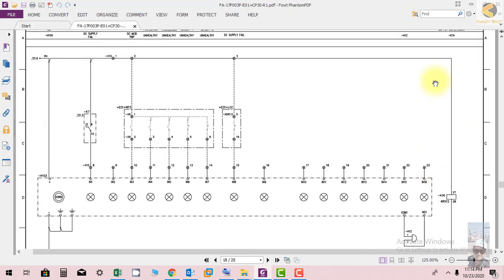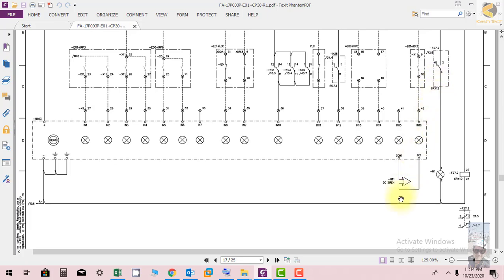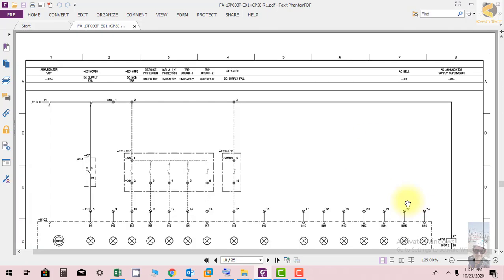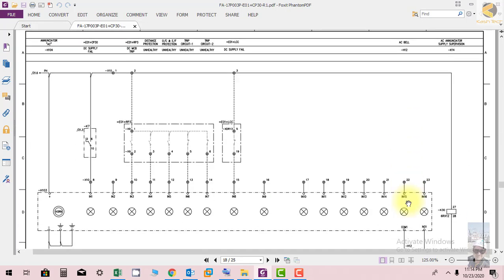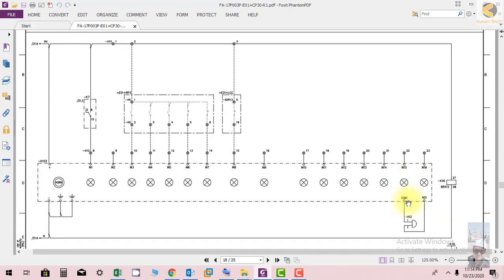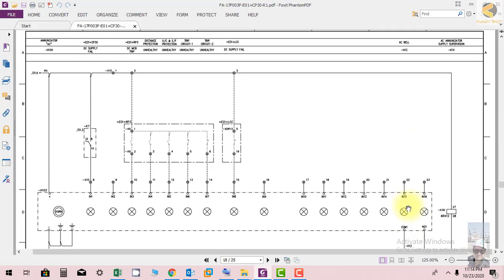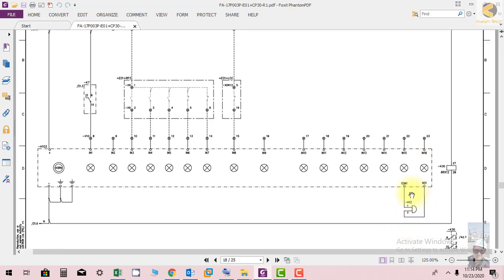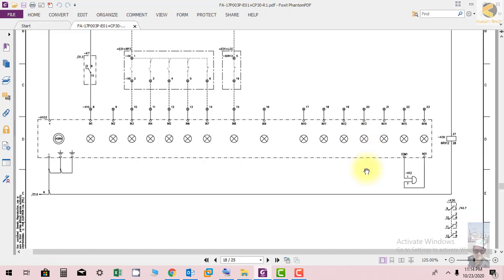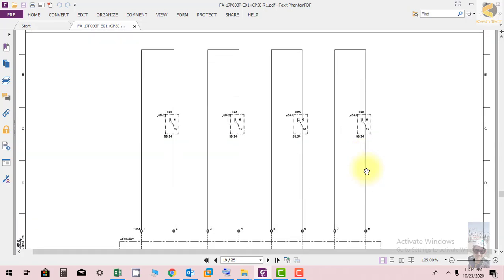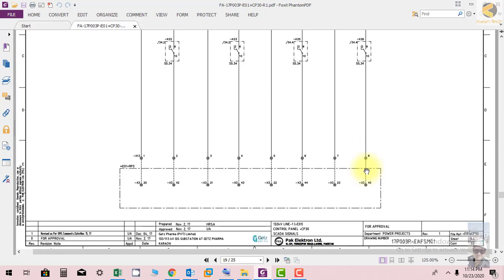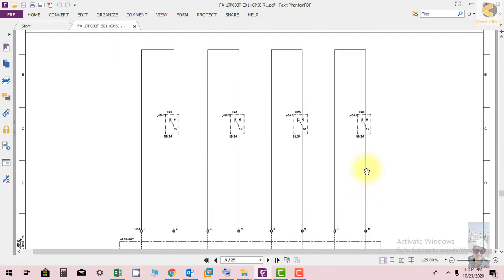For DC, we are using a siren. If the siren sounds, the alarm is coming from DC. For AC, a bell rings. If there is an alarm on the AC annunciator, the operator immediately knows whether the alarm is from DC or AC and can take action accordingly. These signals are going to SCADA.